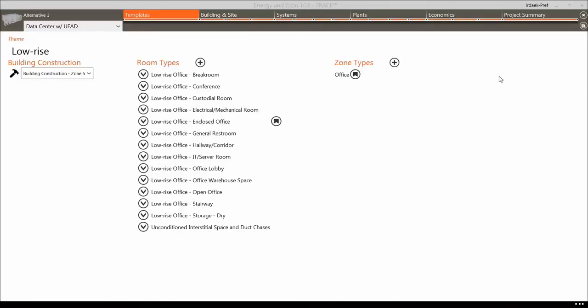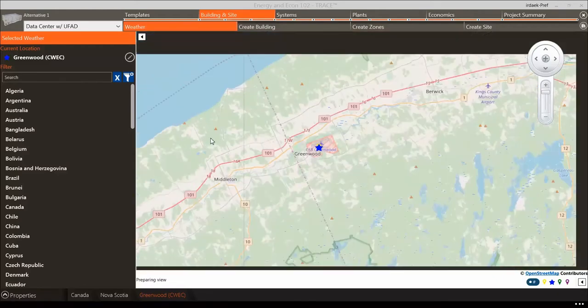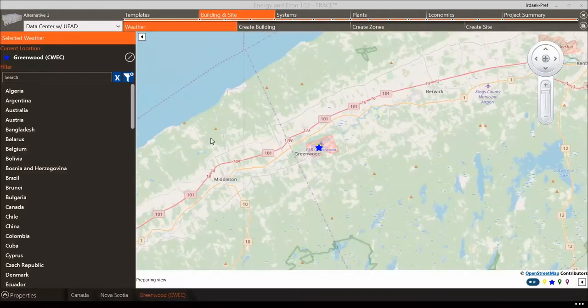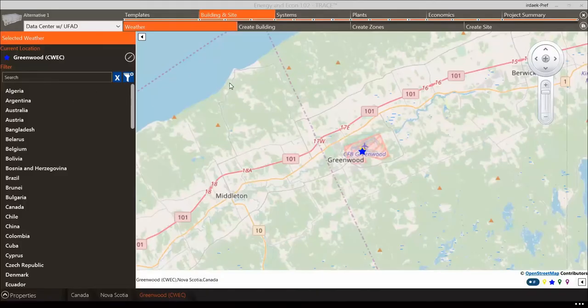Let's go back to the Building and Site section to discuss analysis weather from within the Weather tab. The location Greenwood in Nova Scotia, Canada remains as our weather location from Load Design 101. There are no interface differences between load and energy in the Weather section, so there is no need to adjust anything here. However, the type of weather used for an energy analysis is much different: load design uses a design weather profile as defined by the ASHRAE Handbook of Fundamentals, whereas an energy calculation uses analysis weather, which utilizes an 8760 full-year weather profile.